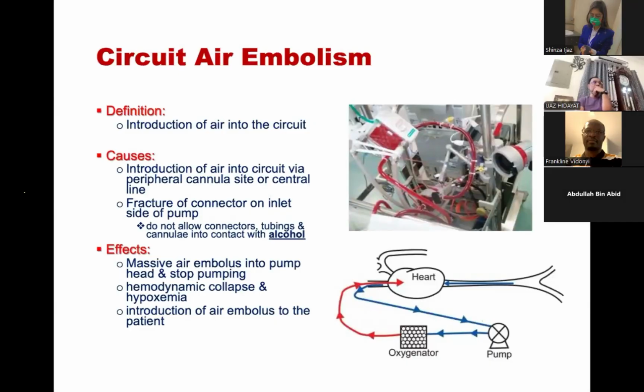Usually in your extracorporeal circuit, and especially on the membrane, you will find hydrophobic ports available. If your machine is alarming, there is a minor error in the circuit, and the flow is not fluctuating and saturation is maintaining, it is not affecting the flow, RPM and pressures, and even the patient saturation is maintaining, but still your machine is showing air in the circuit. In that type of situation, you need to open the hydrophobic port, which is going to help remove the minor air in the circuit without any intervention. Just remove the yellow.